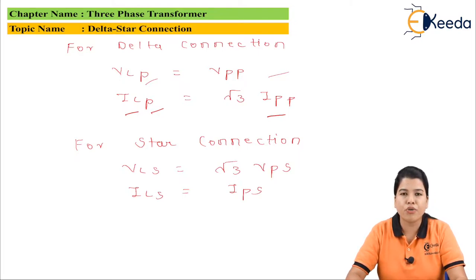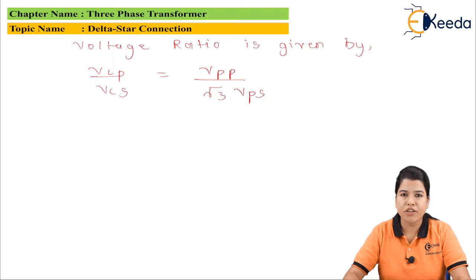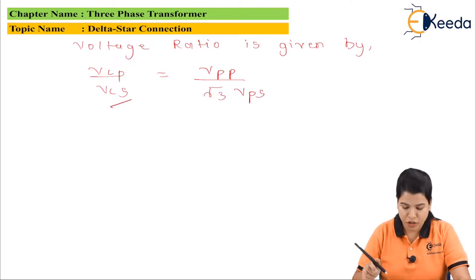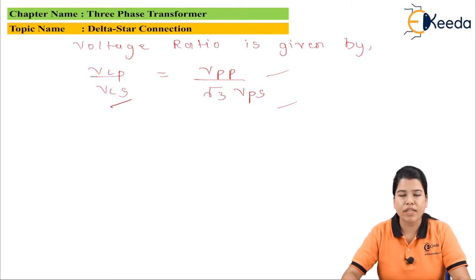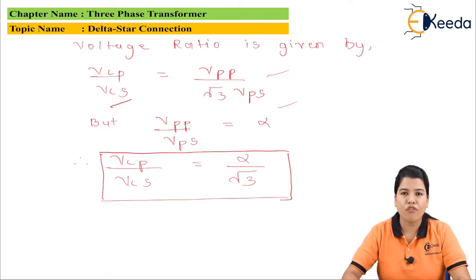If we want to calculate the voltage ratio and current ratio, the voltage ratio is given by: VLP divided by VLS equals VPP divided by root 3 times VPS. Since VPP divided by VPS equals alpha, we can modify this equation. Therefore, VLP divided by VLS equals alpha divided by root 3. This is the voltage ratio.